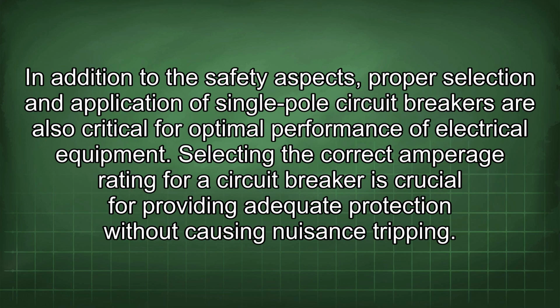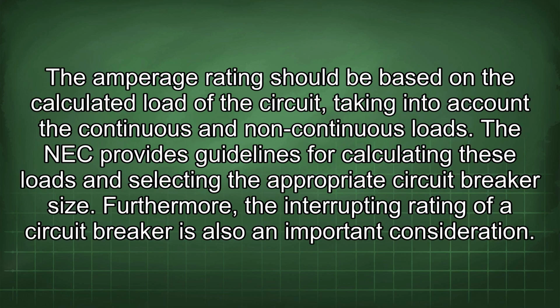In addition to the safety aspects, proper selection and application of single-pole circuit breakers are also critical for optimal performance of electrical equipment. Selecting the correct amperage rating for a circuit breaker is crucial for providing adequate protection without causing nuisance tripping. The amperage rating should be based on the calculated load of the circuit, taking into account the continuous and non-continuous loads. The NEC provides guidelines for calculating these loads and selecting the appropriate circuit breaker size.